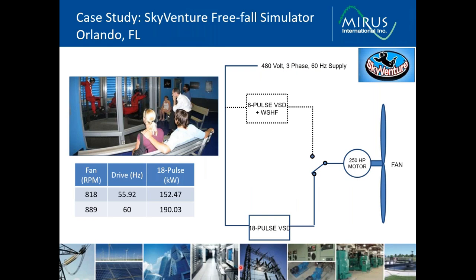In a field example where comparisons were done between a passive filter and 6 pulse drive and an 18 pulse drive, again, it was the skydiving simulators. Here they had been using an 18 pulse drive system to feed the fan motors. And our customer, who was packaging the filter with their 6 pulse VFD, wanted to show the difference and compare the two, so they set up this field situation. When it was running as an 18 pulse drive, there were two fan speeds. At the higher fan speed, or 889 RPM, the drive was running at 60 hertz and drawing 190 kilowatts. At the lower speed, it's just under 56 hertz and 152 kilowatts.